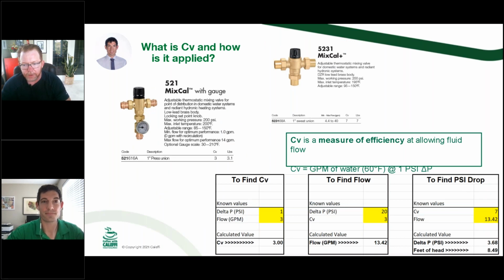So the other thing that's really important and gets overlooked, it doesn't matter whether it's a mixing valve or just simply a zone valve, is the CV. So Max, walk us through the whole CV and how that's important here. Okay, so let's say that you size the job and it's 1-inch pipe. It's the only thing you need, a 1-inch mixing valve. Which 1-inch mixing valve do you need?